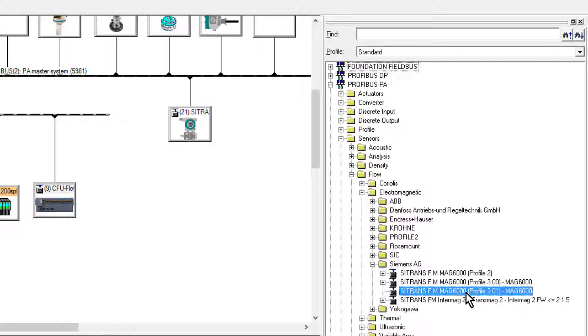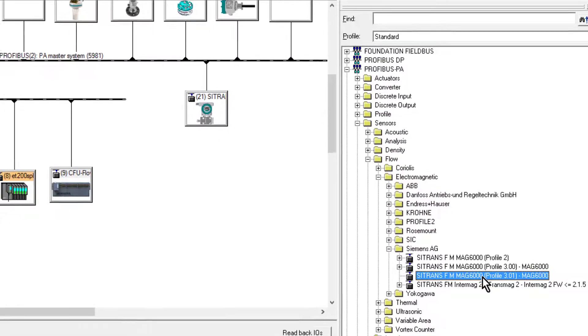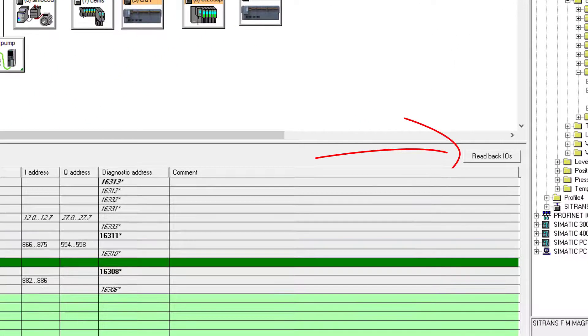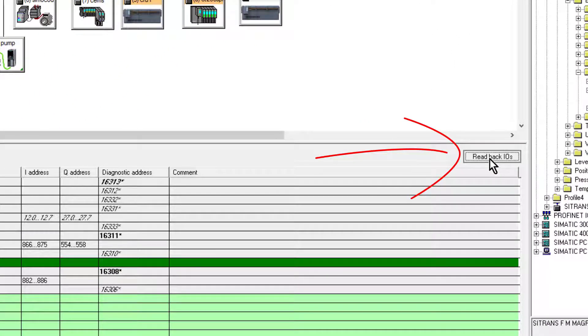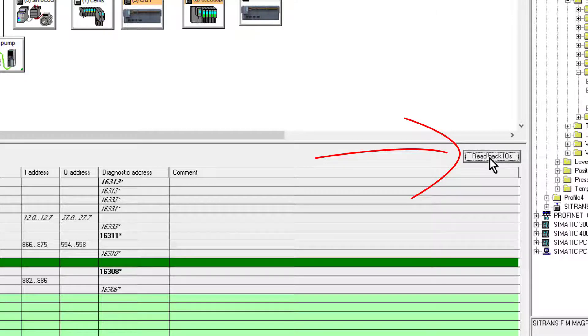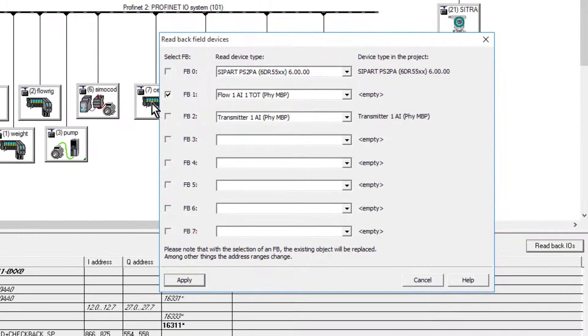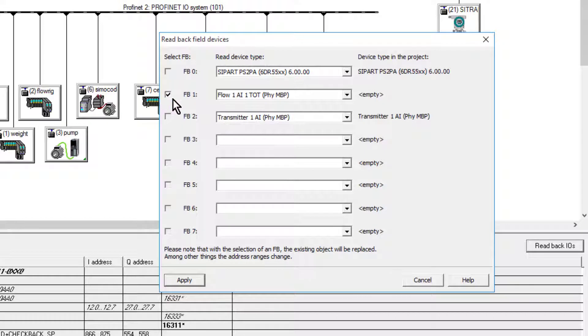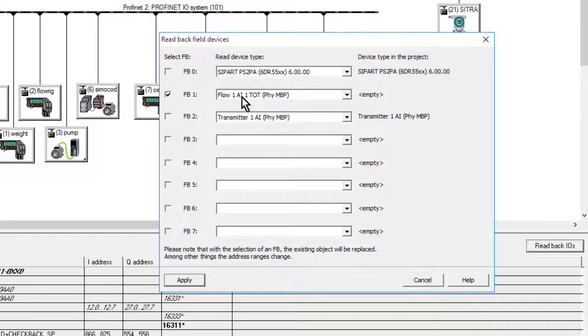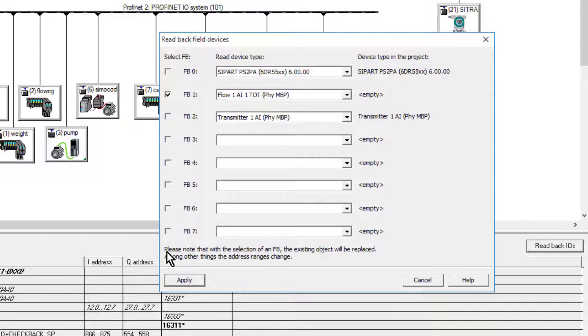But the beauty of having the Compact Field Unit in PCS7 is we get this readback option. So if I click on this, it can see that this channel here is a flow meter with a totalizer and one analog input. It's already read that from looking online, so I can apply that to my project.